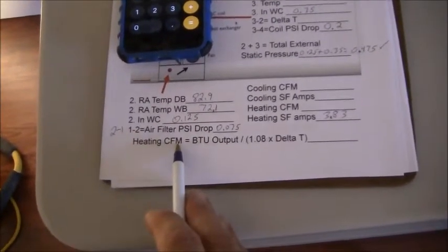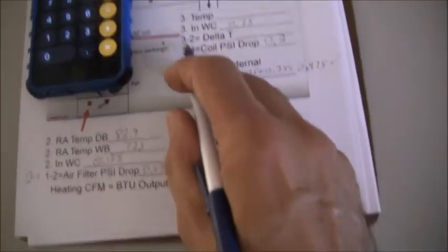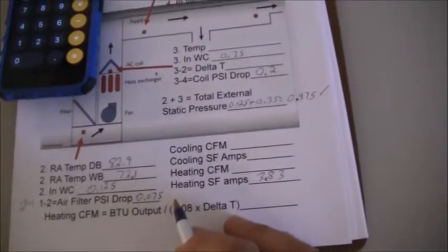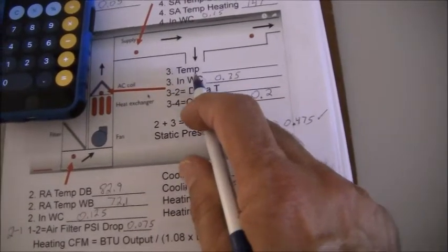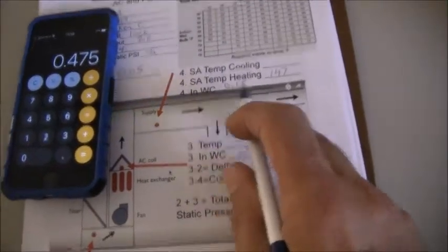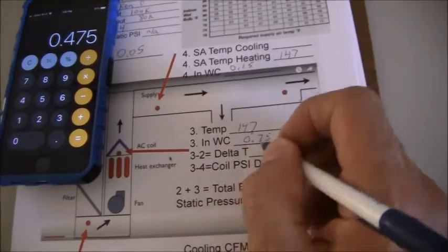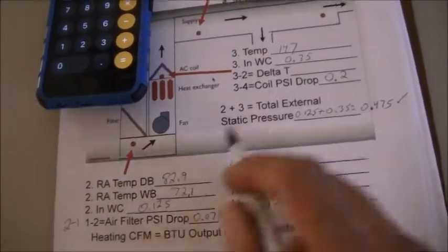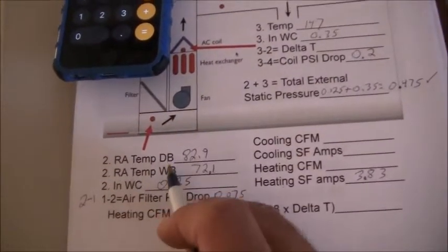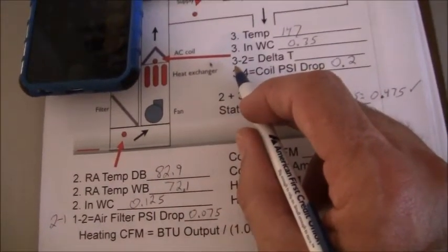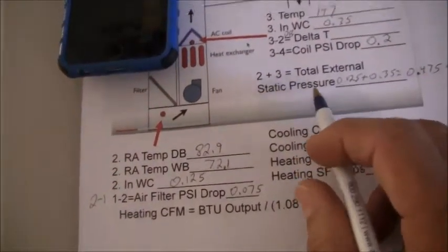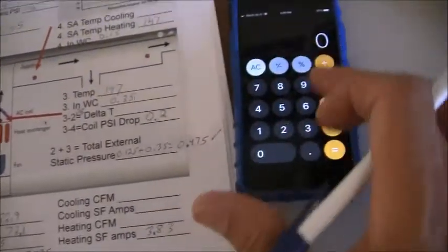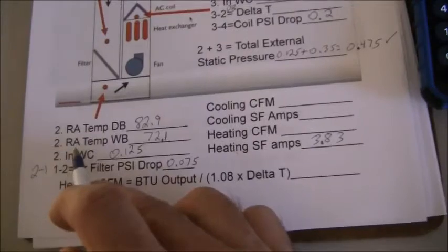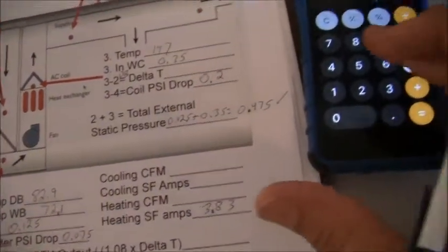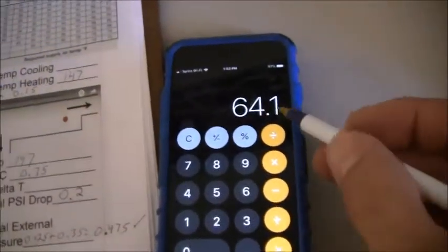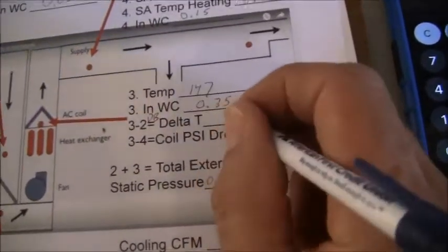Now let's figure out the heating CFM. So what is the delta T? The delta T is 3 minus 2. 3 is the same as this one, 147. So 147 minus 2, which is dry bulb, not wet bulb. So 3 minus 2 dry bulb is 147 minus the return air temperature dry bulb, 82.9. That equals 64.1. So that delta T is 64.1.